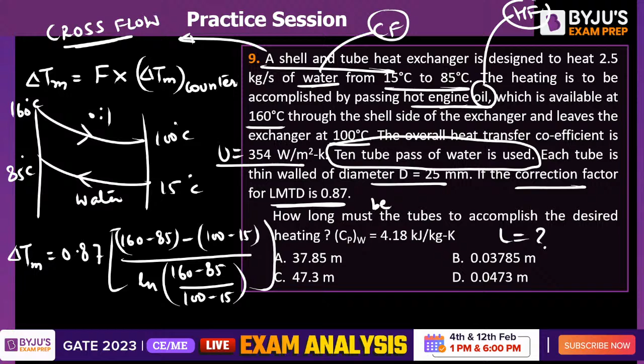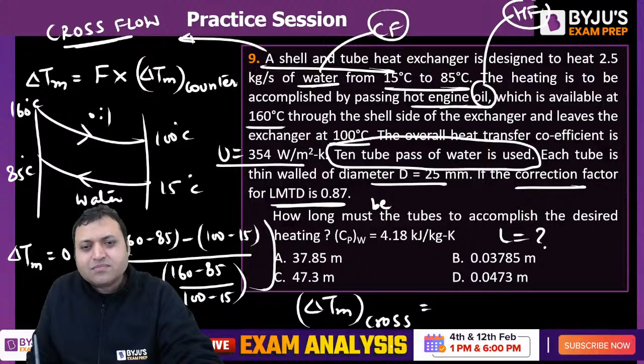Can you get me the LMTD for this heat exchanger? What is the value of the LMTD for this shell and tube type, or cross flow, heat exchanger? What is the LMTD? Are you getting 79, or is it 69.5? Do not forget to multiply with 0.87. If we multiply with 0.87, it will be 69.5. Malesh, you forgot to multiply with 0.87 because it is not counterflow. It is actually the cross flow heat exchanger.